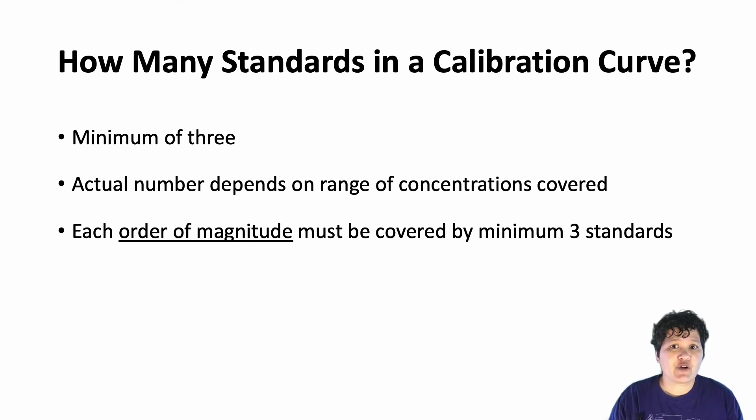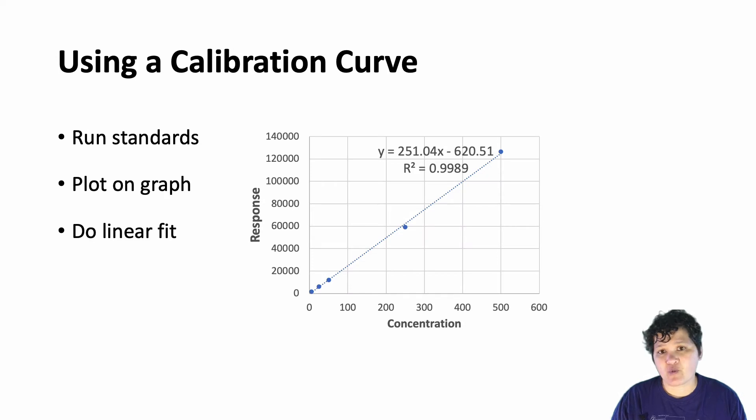So when you make a calibration curve, you're basically going to create your standards and run them on the instrument. You're going to graph the concentrations of the standards on the x-axis and the instrument responses on the y-axis, and then you do a linear fit. You want to make sure that you have both the equation for the line and the r-squared for your linear fit. You're going to use the equation for the line to calculate the concentrations of your samples, and the r-squared is a measure of quality for your external standards. The closer your r-squared is to 1, the more linear your calibration curve is, and the more trustworthy your measurements are going to be.